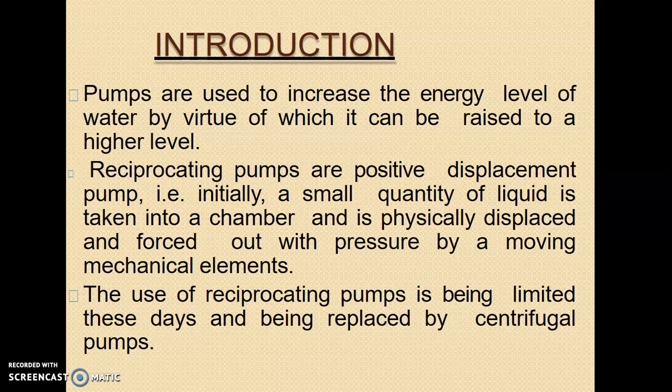So positive displacement means what? A particular quantity of liquid is physically displaced and forced out with certain pressure by a mechanical system, and that is called positive displacement. And why the word positive? Positive means a particular quantity of liquid is positively displaced in the forward direction. So reciprocating pumps are positive displacement pumps.